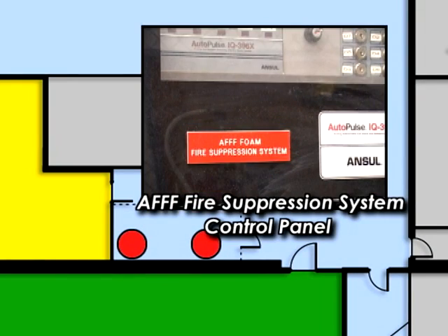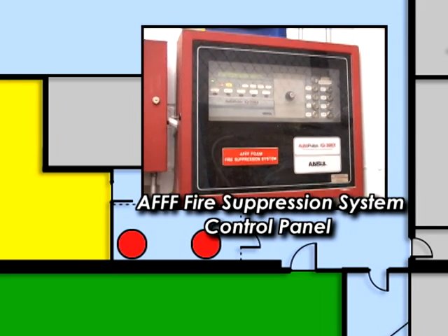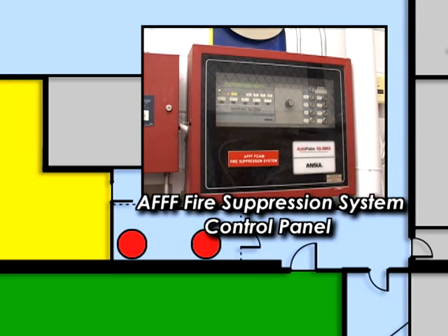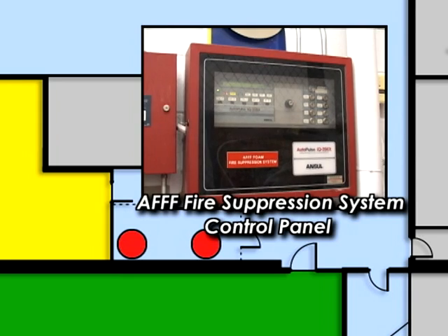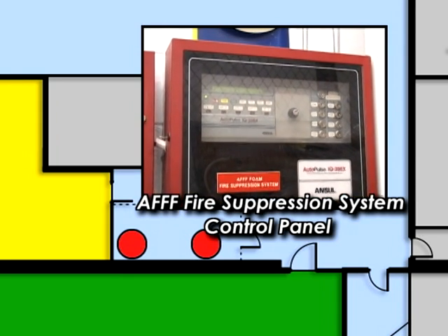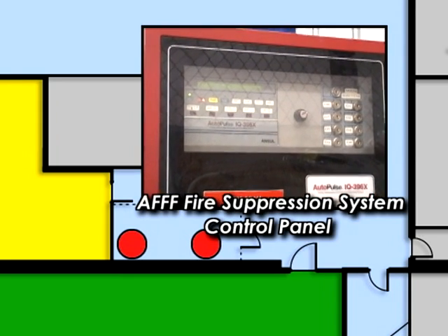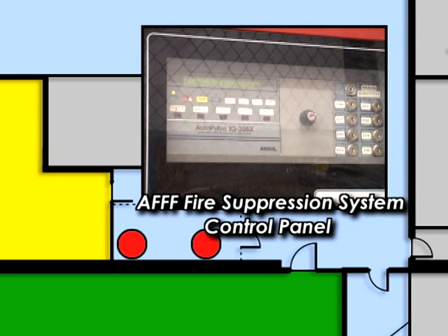The control panels for the AFFF equipment are located in the west warehouse, adjacent to where the AFFF tanks and valves are located. This permits access for maintenance and operation of the panel without entering the spaces served. This is designed to minimize risk to responding emergency personnel if the system must be accessed for information or reset during an emergency.